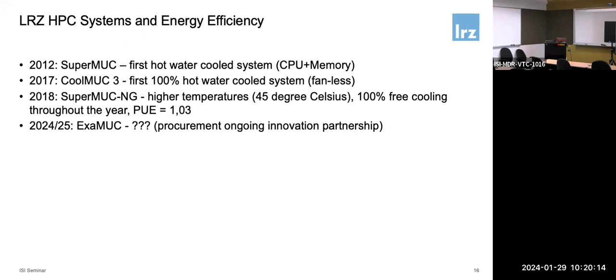The one means this is the power we need for running the system and doing the computation, and what's after the decimal point is what we need for cooling. So we need 3% extra energy to cool the system — exactly what's needed to run the pumps to get the hot water to the roof, let it cool, and use it again for cooling. That's a pretty good number, I believe. Is there anybody better? I haven't met one so far, but there might be — it's hard to imagine. And we're even improving that further, I'll come to that in a second.